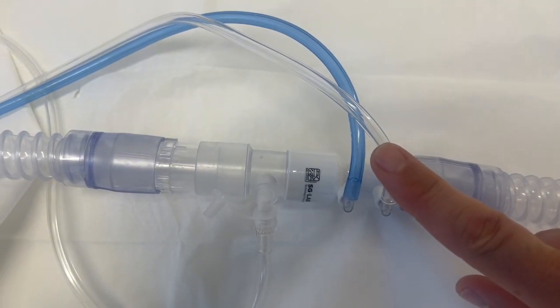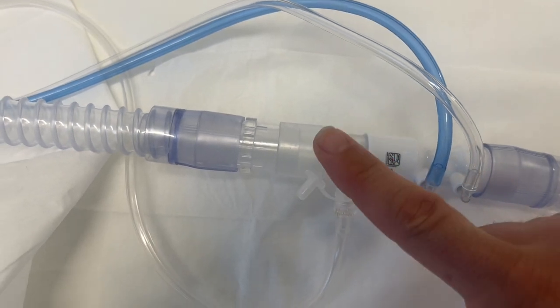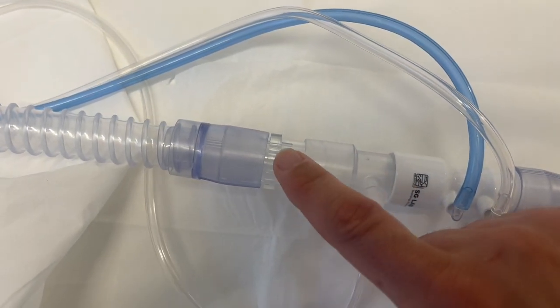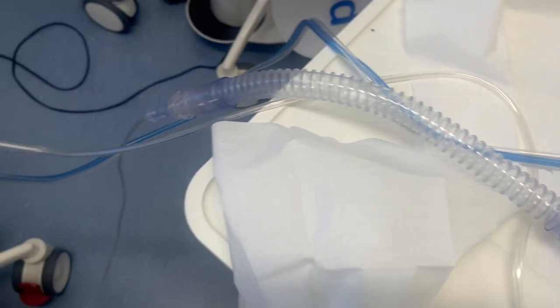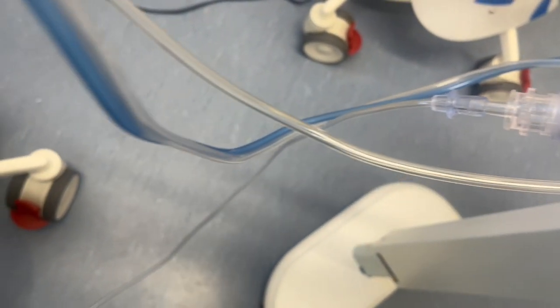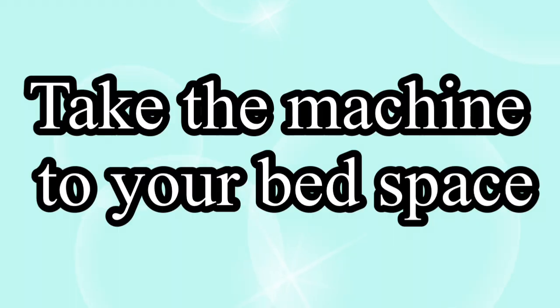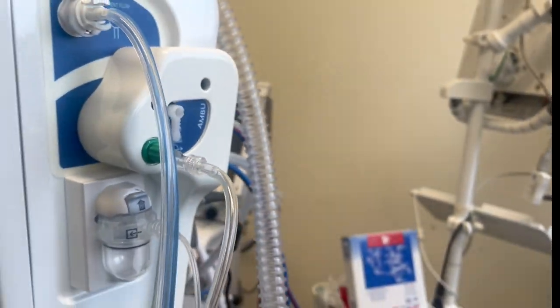Sample line on the end of the larger part of the test circuit, flow measurement line, nitric injection adapter. An adapter allows you to put the shorter part of the test circuit on, another adapter that connects to tubing that will go to your oxygen flow meter. A sticker will be on the machine to ensure you're using clean disposables. This can now be disposed of.